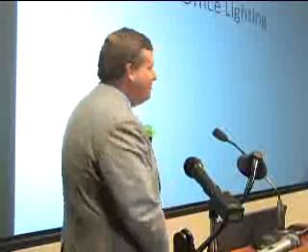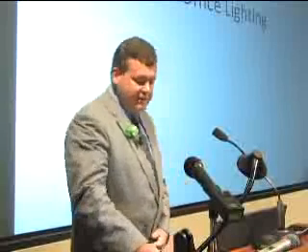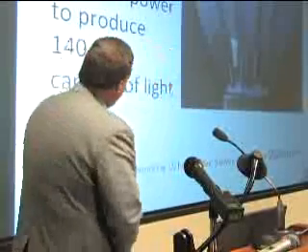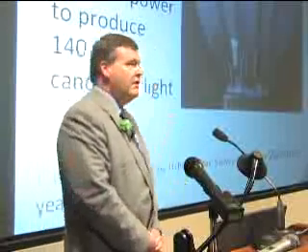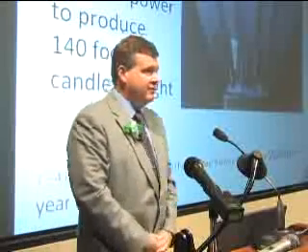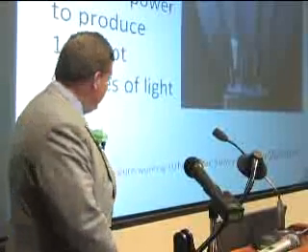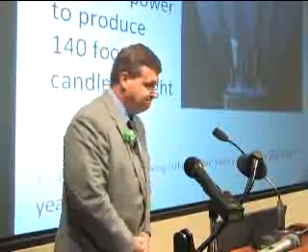So I'm going to talk about some basic office lighting. Obviously, everyone has lighting in their office, and these are some real basic ideas that generate some pretty significant savings. This is the old technology. 20 years ago, this was the latest and greatest, newest thing. 4-lamp T12 fluorescent technology consumes up to 192 watts of power and gives a foot candle reading of about 140 foot candles. One 4-lamp T12 fixture working 10 hours a day, 5 days a week is going to cost you an average of $52 a year to operate. And that's one.